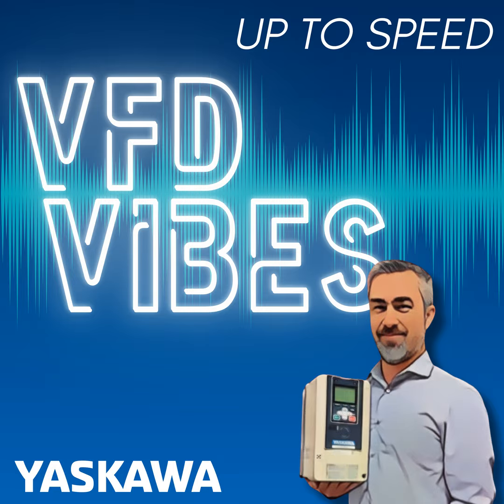So you start from the ground up building your system so that you're dealing with these things, with EMI, with harmonics, with whatever. Because it's really expensive to come along later and say, hey, we got too much EMI or we got too many harmonics. So the good thing is to know you're going to have to deal with these early on. And frankly, the reason that solidly grounded 3-phase systems, the typical Y connection with a solid ground, is also a pretty good way to deal with EMI in the system.